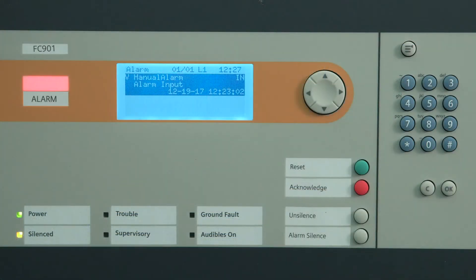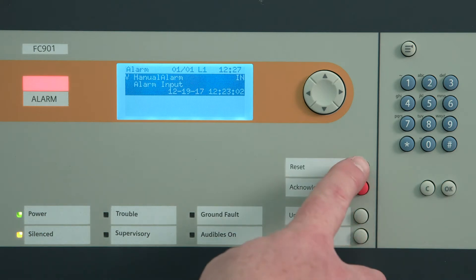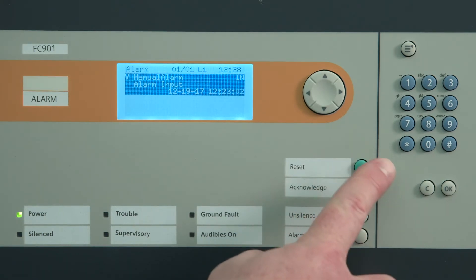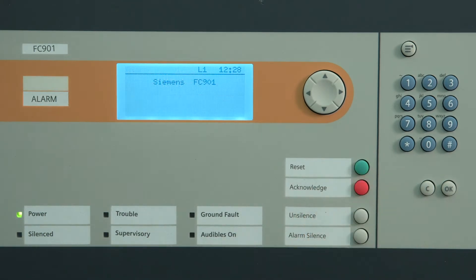You will now see that the alarm silenced LED will be lit. Some things to keep in mind: do not reset the panel until the alarm has been cleared, and alarm silenced inhibit, if set, prevents the alarm from being silenced for a predetermined amount of time. Now to reset the panel after alarm — when the alarm condition is corrected, return the panel to normal standby operation by pressing the reset button.